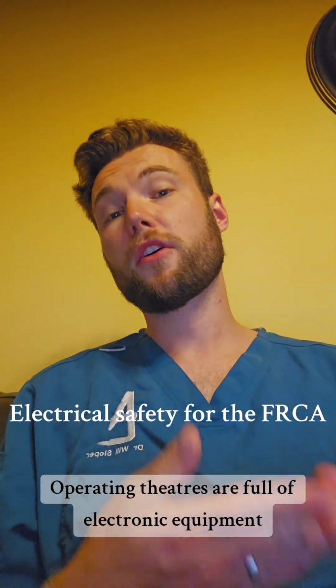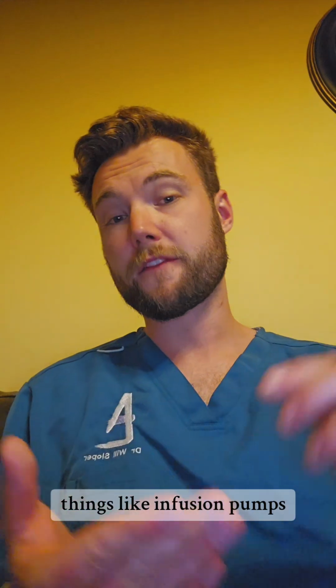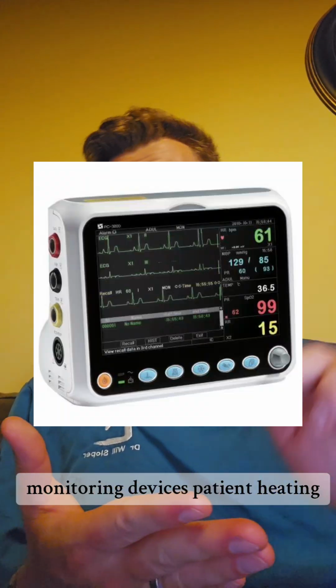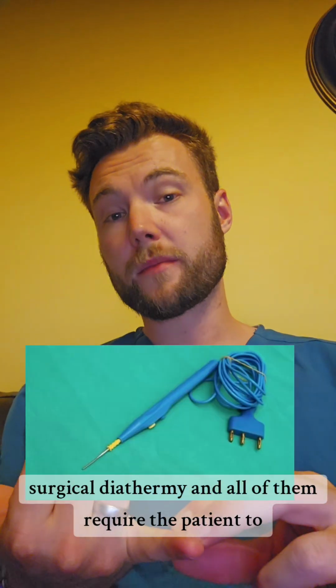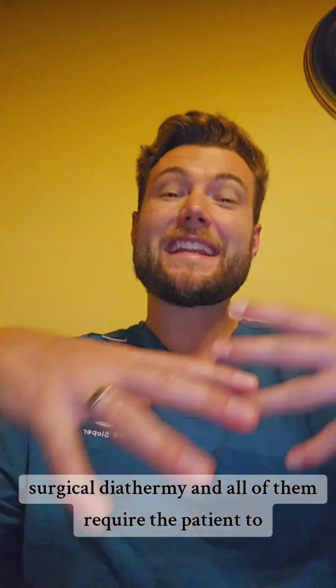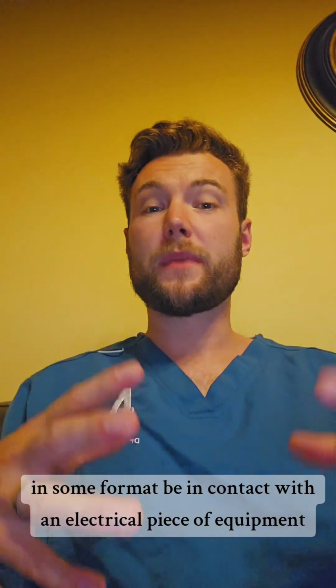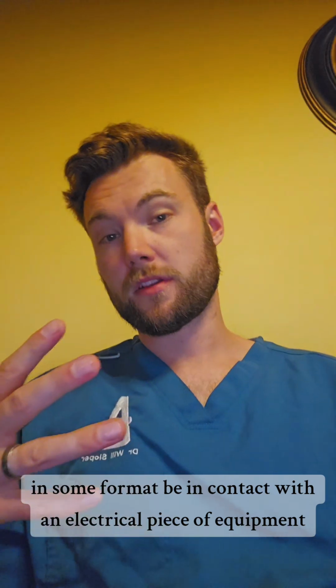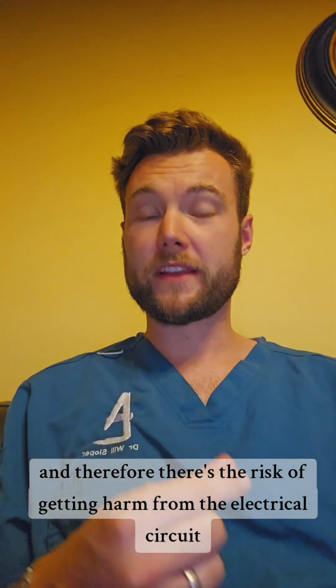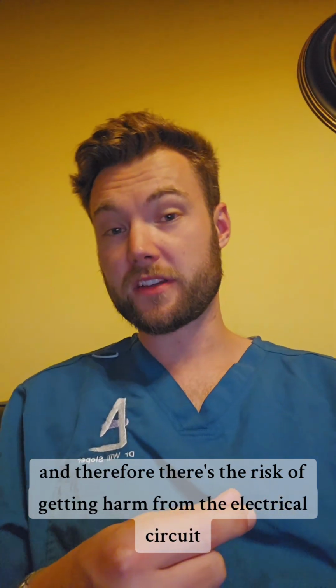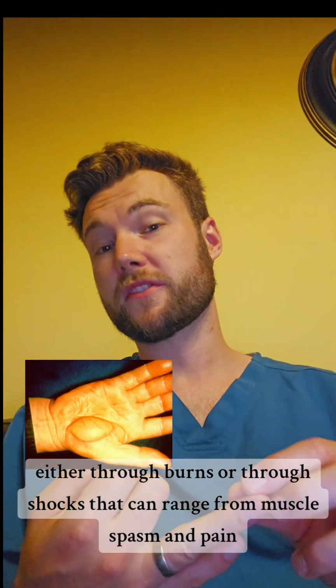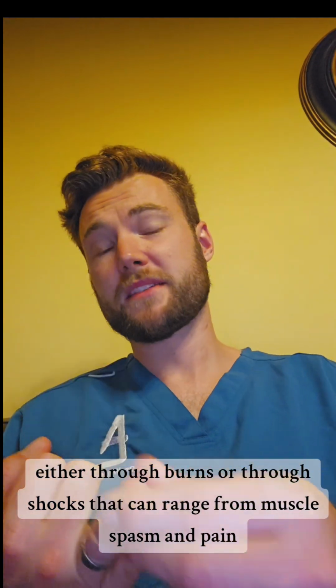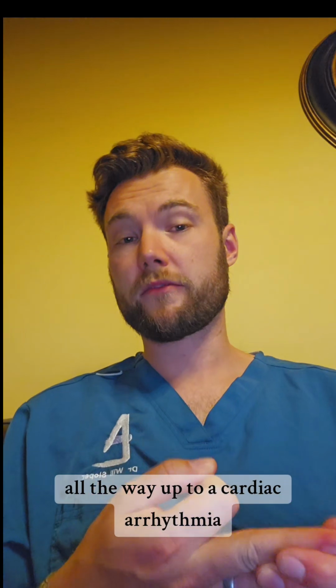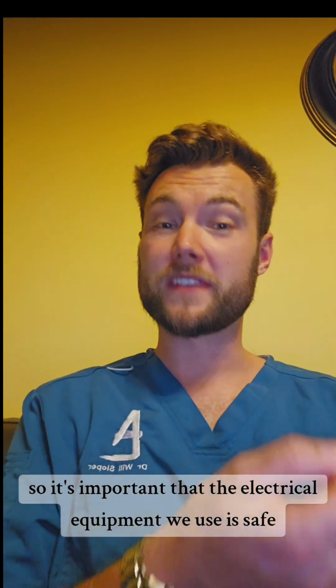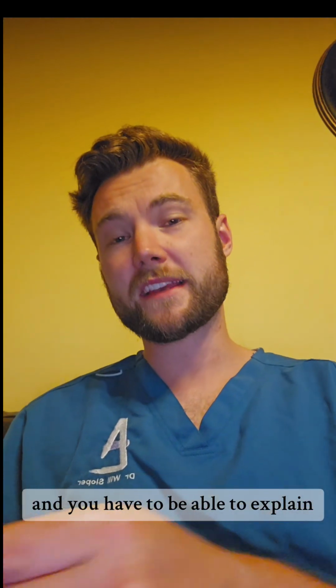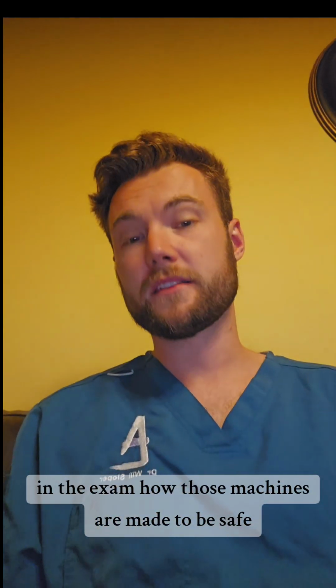Operating theatres are full of electronic equipment, things like infusion pumps, monitoring devices, patient heating, surgical diathermy, and all of them require the patient to, in some format, be in contact with an electrical piece of equipment. And therefore there's the risk of getting harm from the electrical circuits, either through burns or through shocks that can range from muscle spasm and pain all the way up to a cardiac arrhythmia. So it's important that the electrical equipment we use is safe, and you have to be able to explain in the exam how those machines are made to be safe.